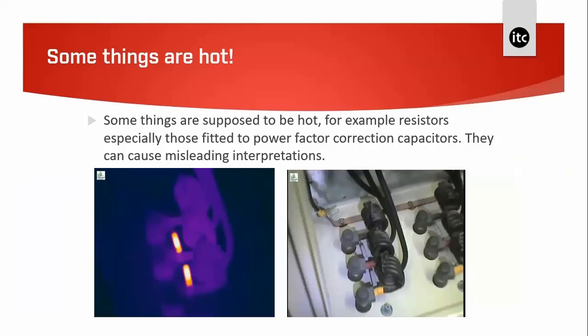When scanning electrical cabinets with an infrared camera, don't confuse the thermal anomaly with something designed to be hot. Resistors — especially those fitted to power factor correction capacitors — can cause misleading hot spots and aren't really a problem. I've seen reports where classification criteria were applied to components like these, and it really is a false anomaly.